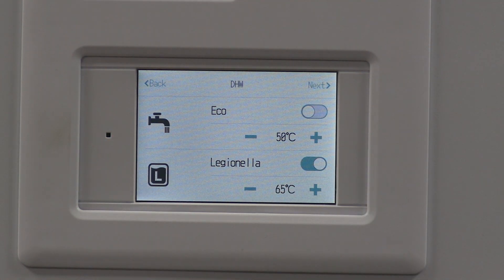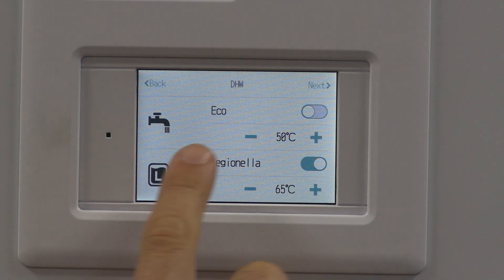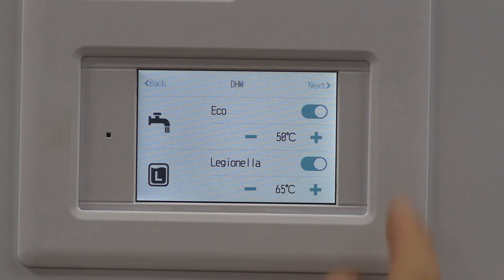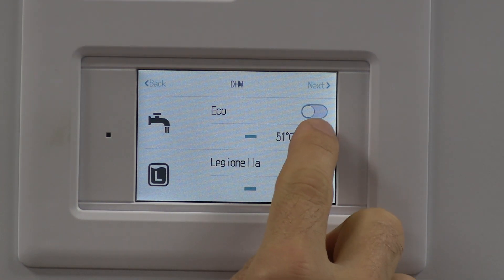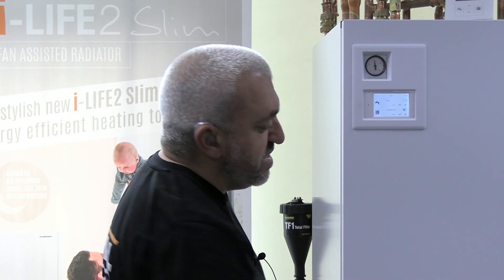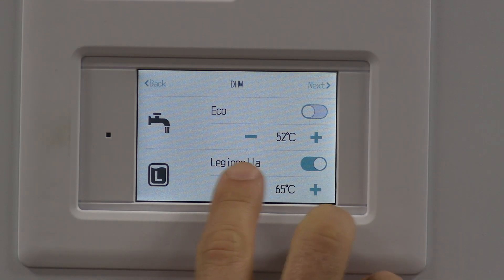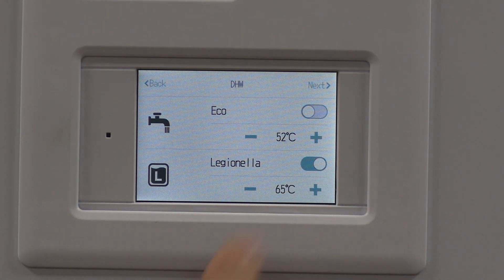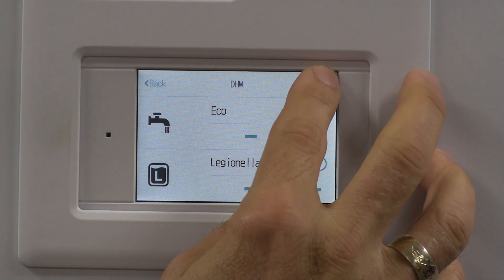Next you've got your hot water and Legionella settings. There are only two settings here: you can set hot water to eco on or off, and then the target temperature of your tank. Eco mode basically means the outdoor unit will run more economically, not ramping up to maximum frequency and therefore running at lower amperage - potentially costing less to run but maybe taking slightly longer to heat the cylinder. Then Legionella is either on or off, with a target temperature for the Legionella function.